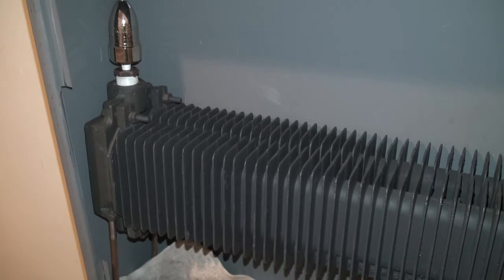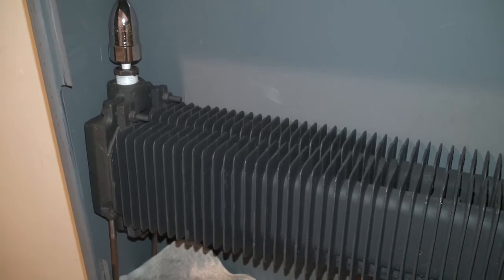Now, I'm not encouraging nobody to go ahead and start boosting their boiler up to 5 to 7 psi. You don't need that much. I recommend no more than about 2.5 pounds of pressure, depending on the system, before you make any adjustments, because people will tell you it's not on your pressure, it's on your venting. And that's true, but that only applies accurately on a properly set up heating system.